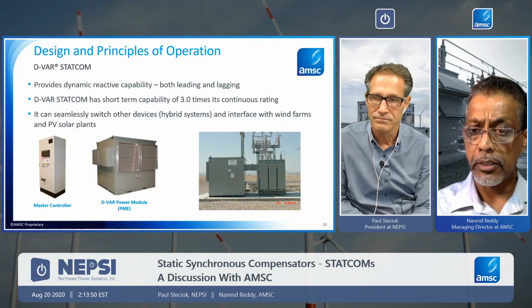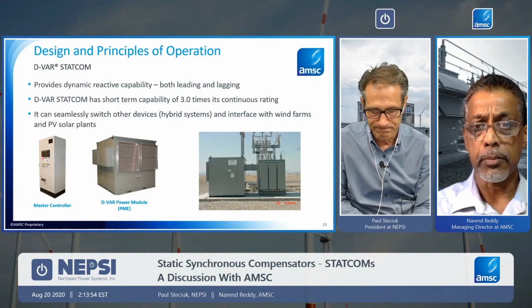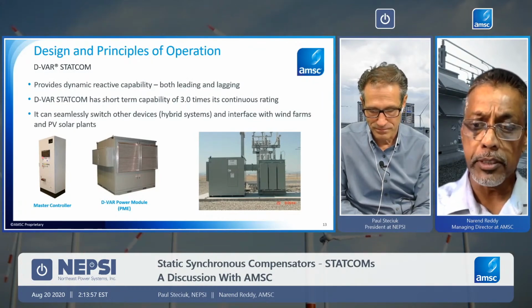The D-VAR STATCOM, in addition to some of the features that we'll talk about, has a short-term capability of 3 times its continuous rating. So essentially a 4 megavar D-VAR STATCOM unit, right out of the box as it's designed and built, is capable of 12 megavar capacitive or 12 megavar inductive for up to 2 seconds. You'd note that STATCOMs are, as I mentioned earlier on, dynamic devices. They're fast acting. And so really their application is to address problems that require very fast, concentrated amounts of VAR support. And this is where the short-term overload really comes in handy.